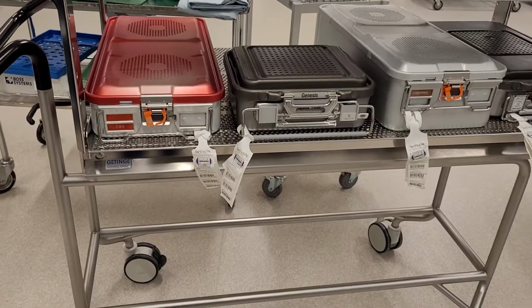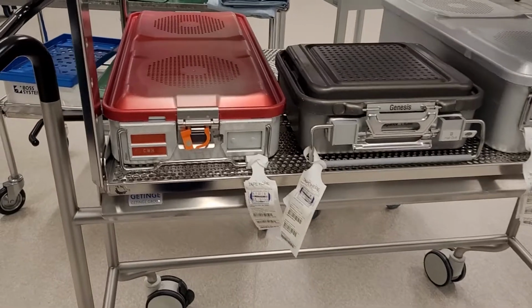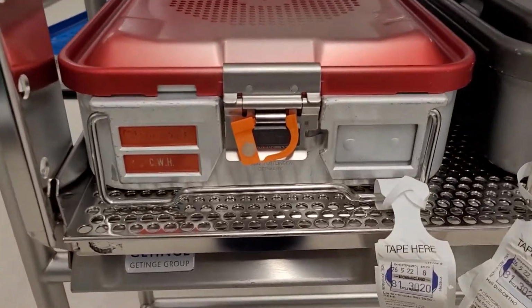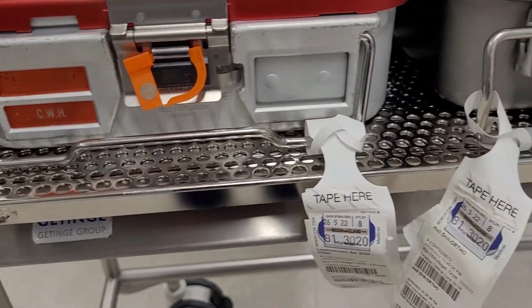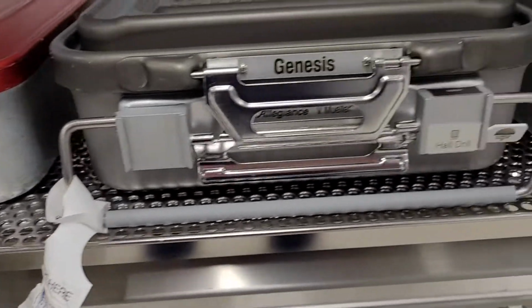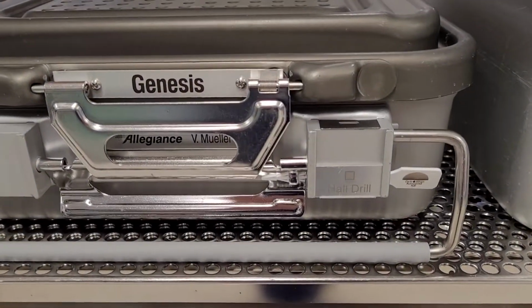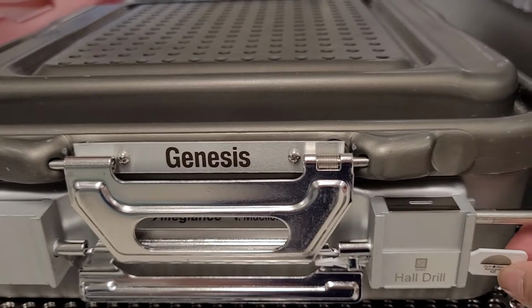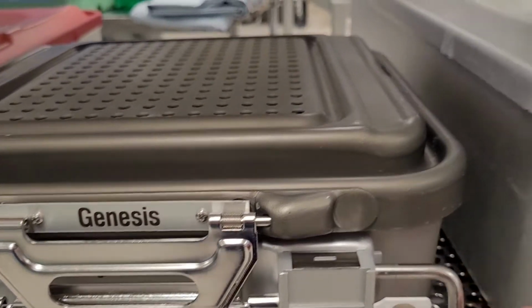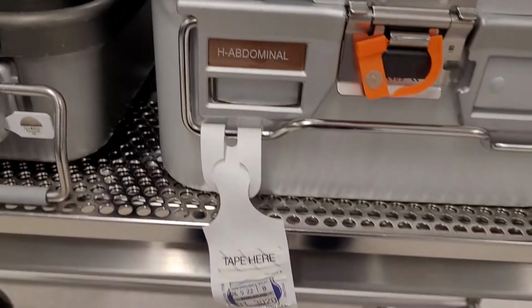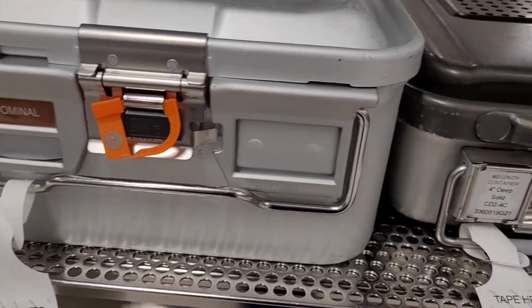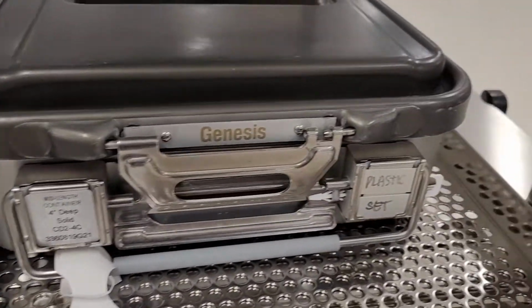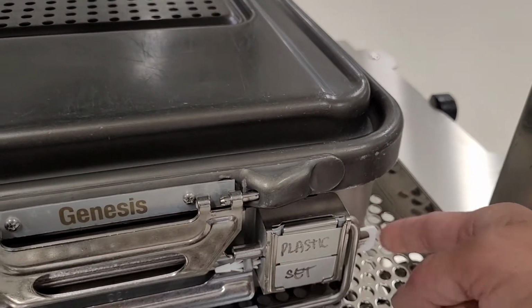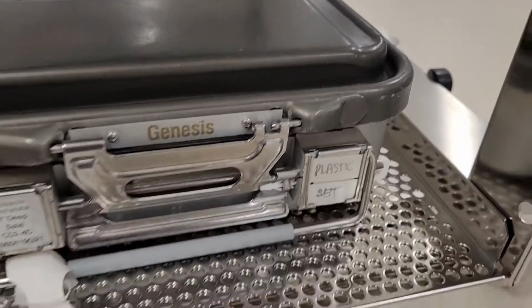After sterilization and storage, but prior to use, check the appropriate color change of the chemical indicator dot on the tamper evident arrows, and gently pull to ensure the filter is in place. If the arrow slips out of the channel, consider the contents of the container not sterile. After surgical instruments are cooled, it is extremely important that they are handled carefully to maintain sterility.